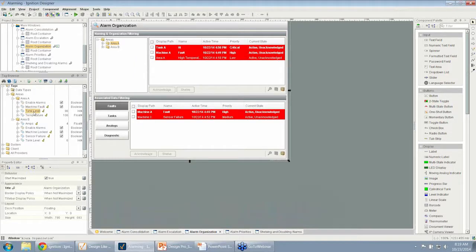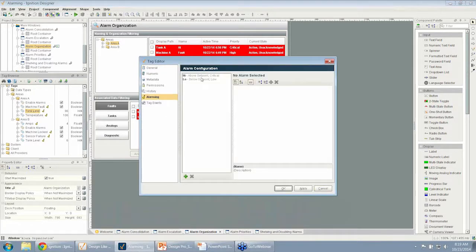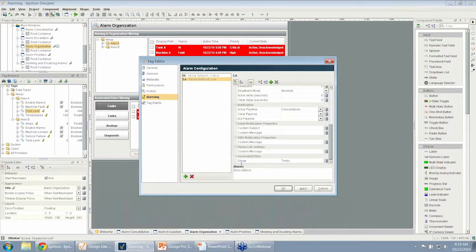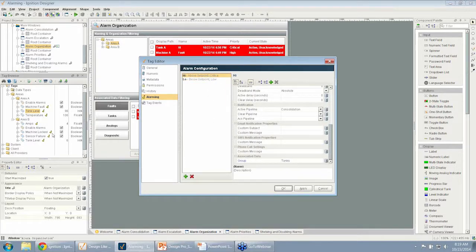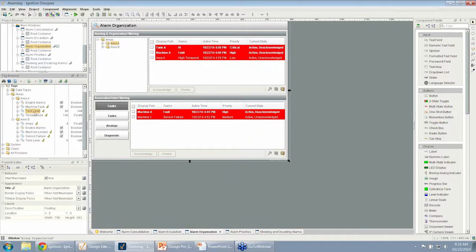If I go to my tank level and look at the alarming, I have the same idea. Here I have a group, and in this case I have it called tanks. I've done that with all these alarms I configured. I can add my own associated data. Whether we organize the tags into folders or use associated data, the idea is that on the screens and through the alarming system, we can use that for filtering.